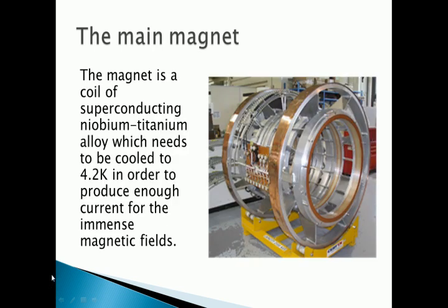Here's a photograph of an MRI main magnet. It's a superconducting magnet made of an exotic alloy, and to make it superconducting you need to cool it down to about 4.2 kelvin. At that temperature you can push current through it with zero electrical resistance, so you can push huge amounts of current through the coils without them getting hot. These sorts of currents are needed to produce a field of one to two tesla — a very strong field produced by very large currents in a very cold machine cooled by liquid helium.